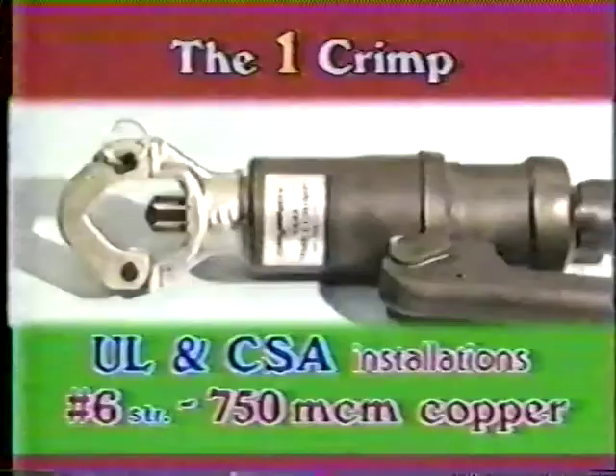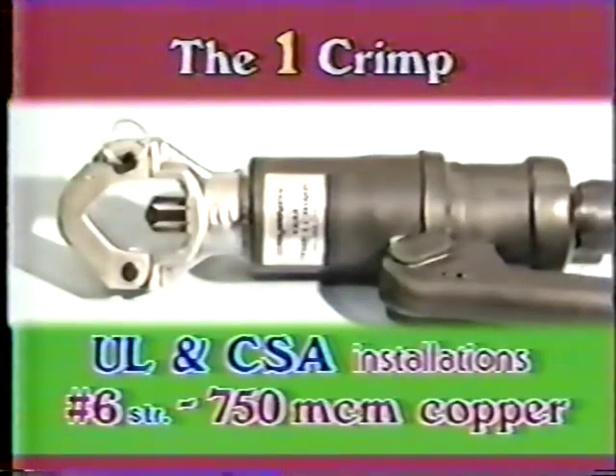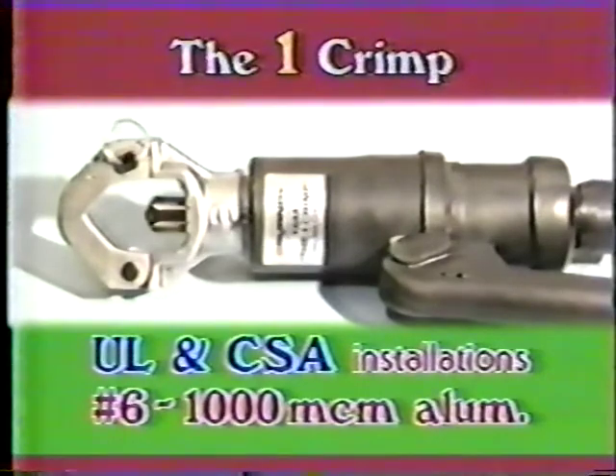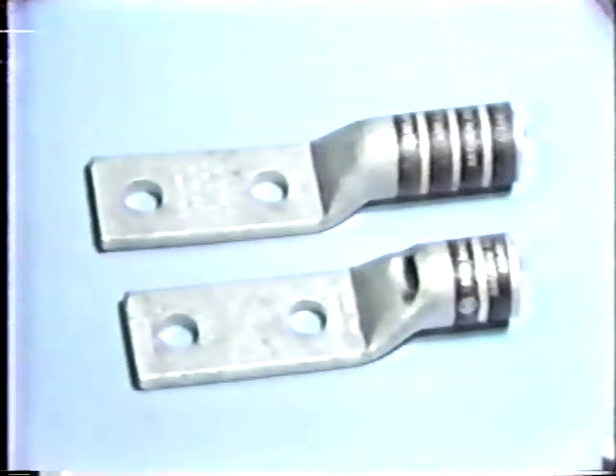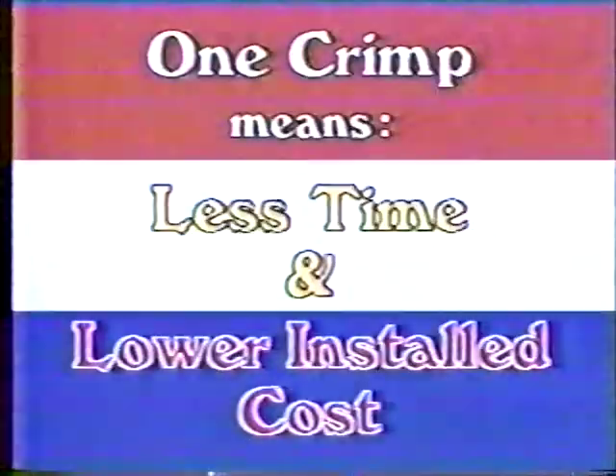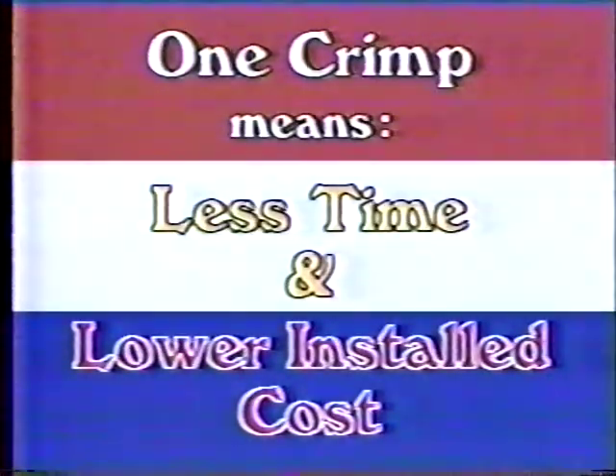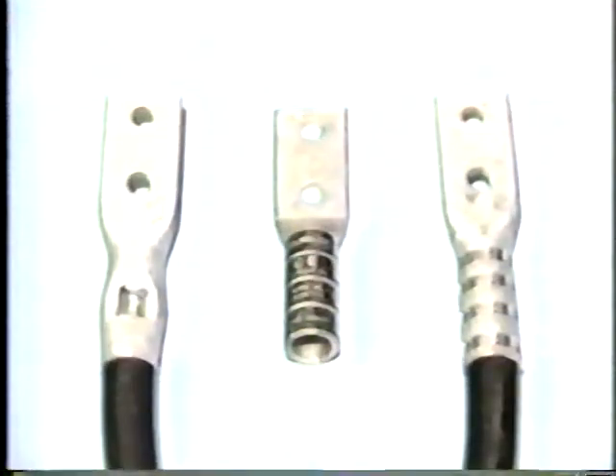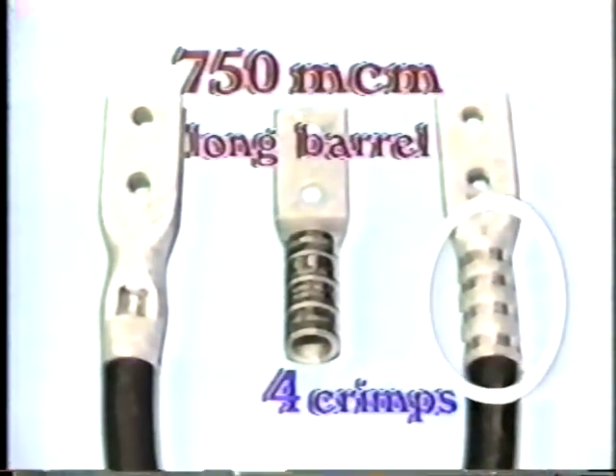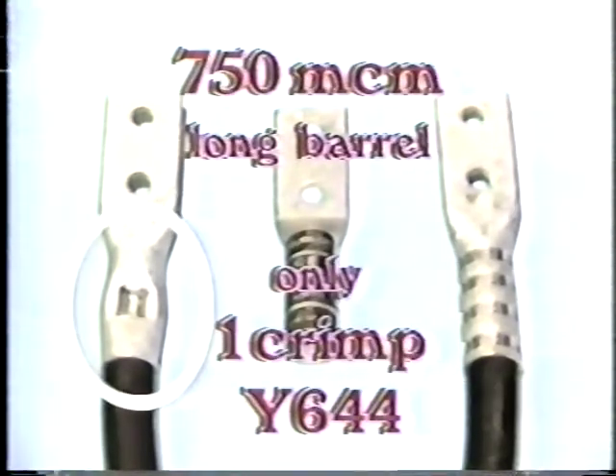This tool will install number 6 stranded through 750 MCM copper and number 6 through 1000 MCM aluminum conductors. With the Y644, short and long barrel connectors require only one crimp to complete the installation. One crimp means less time and a lower installed cost, especially on larger conductors. For example, a 750 MCM long barrel normally requires 4 crimps. However, with the Y644, the installation can be completed with only one crimp.